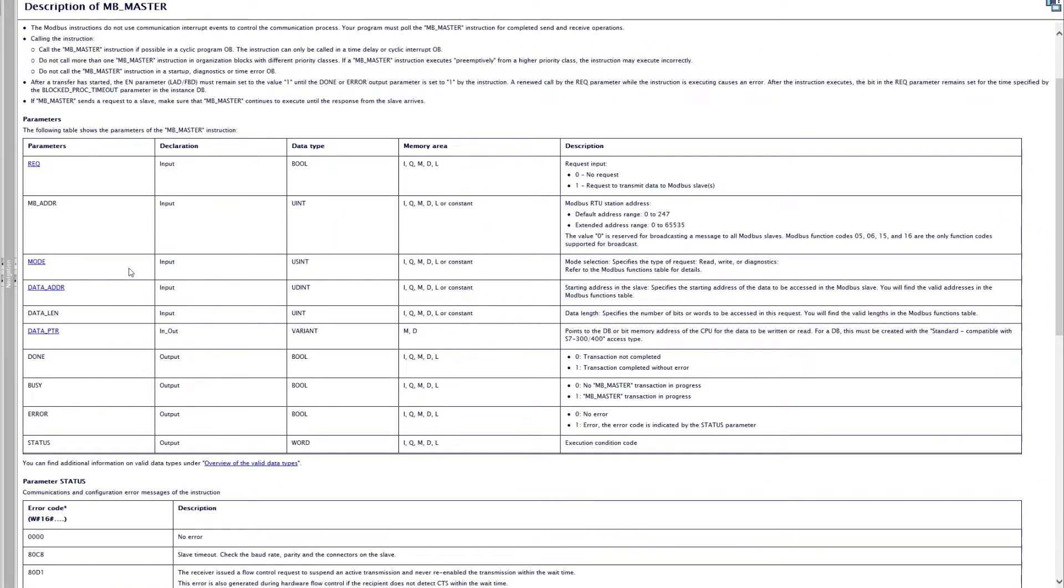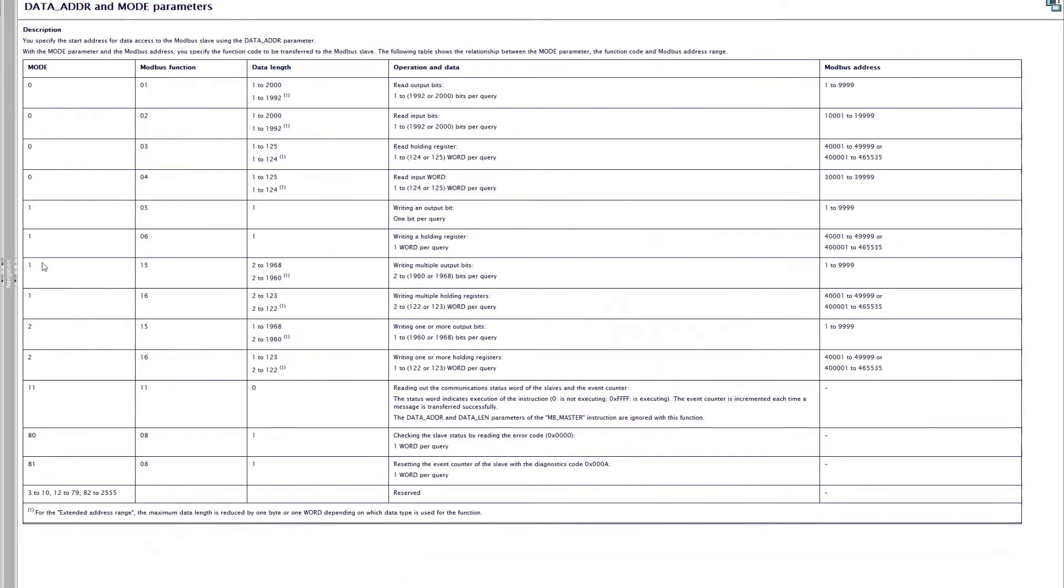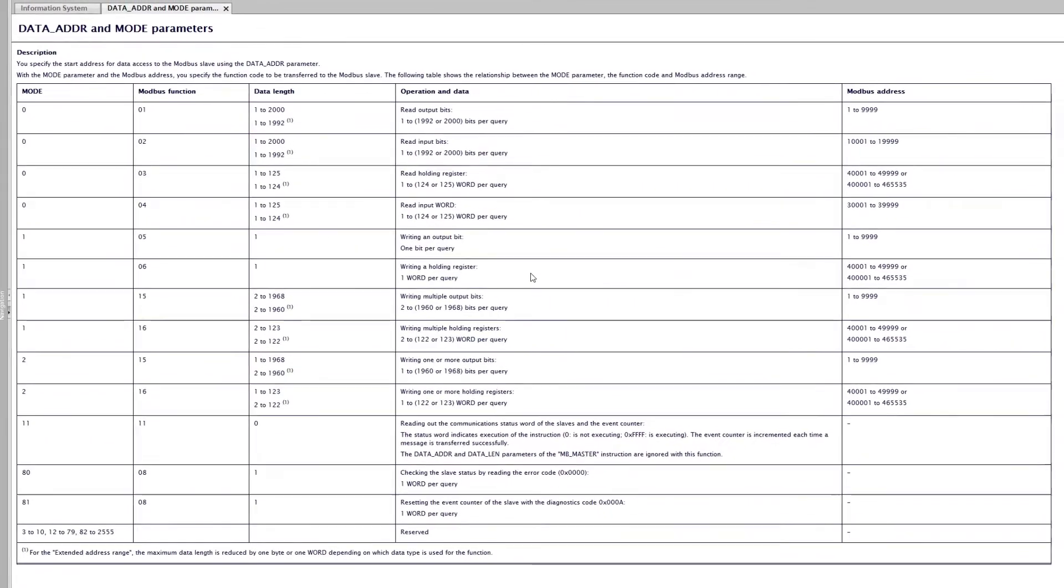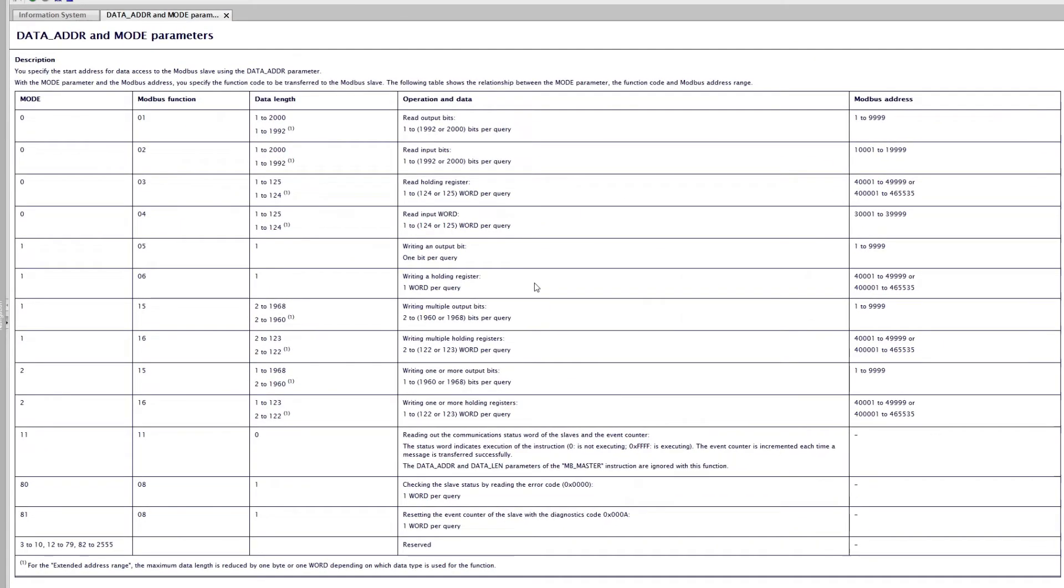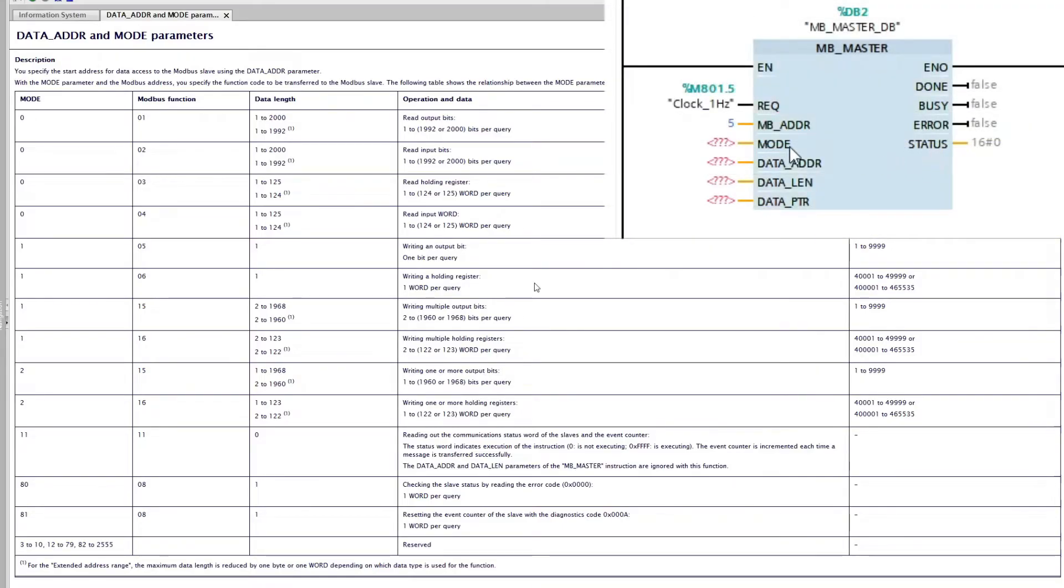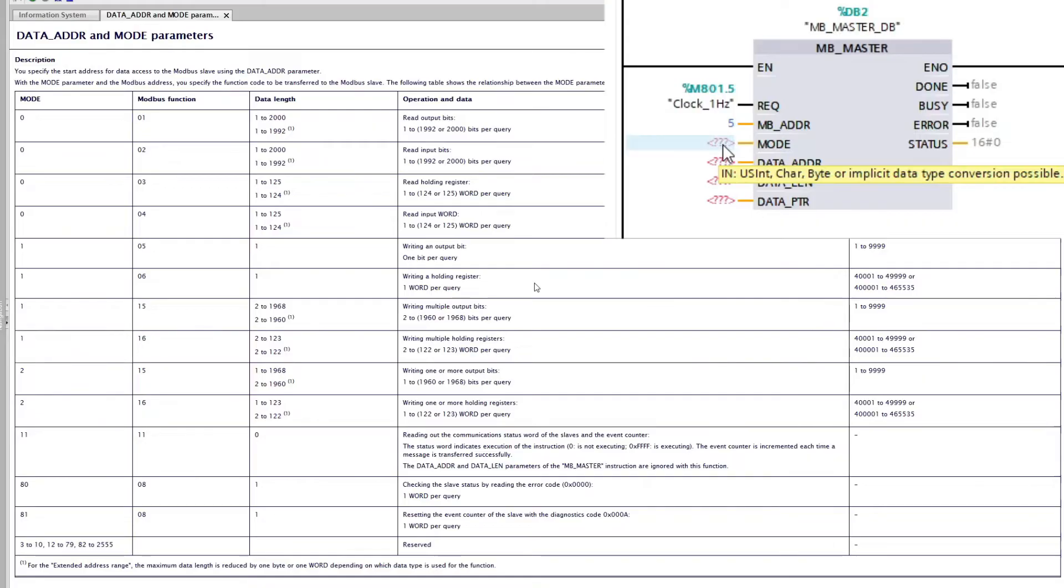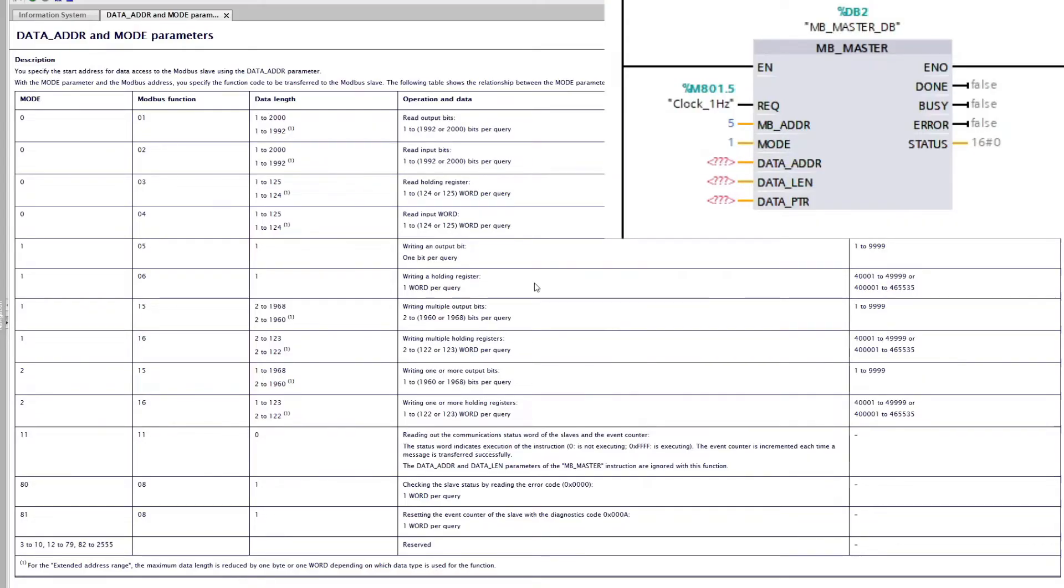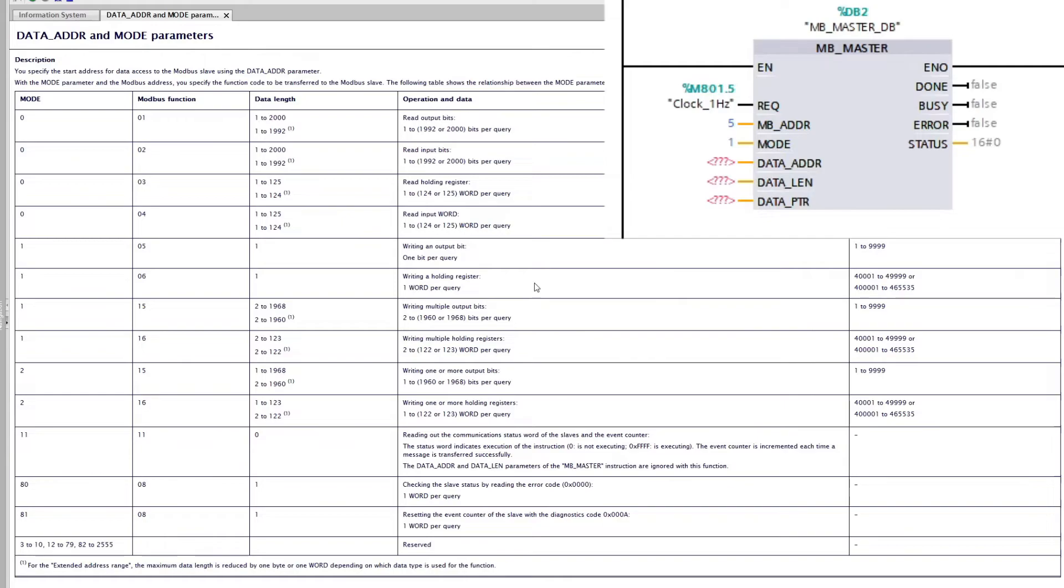If we click on mode we will see how we program the other inputs. Since I want to write multiple holding registers I will be looking at this column. The mode should be set to 1. And the Modbus first address is 4001 and can go all the way up to 65535. Since I want to write from the first Modbus address I will type in 40001.